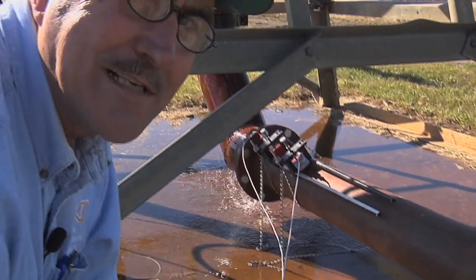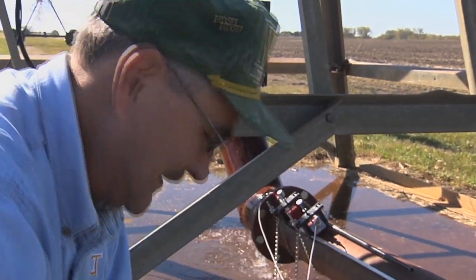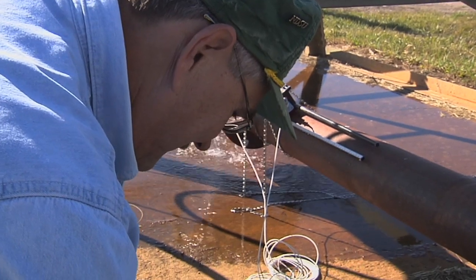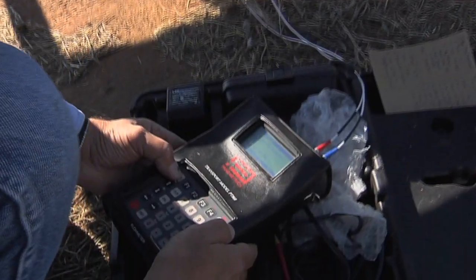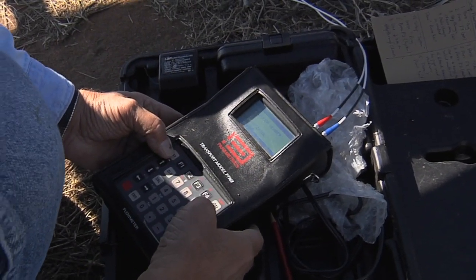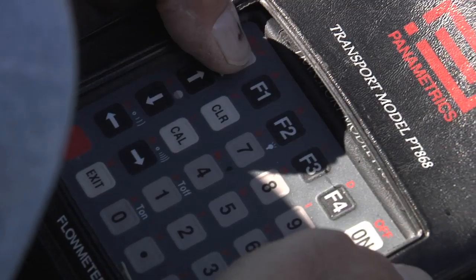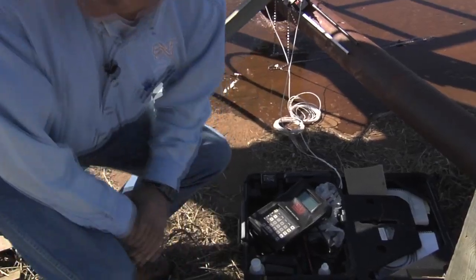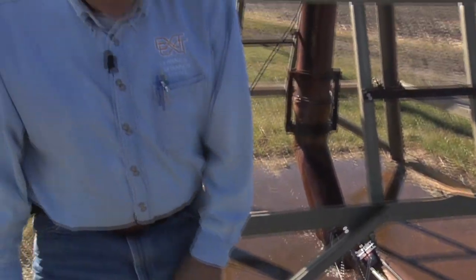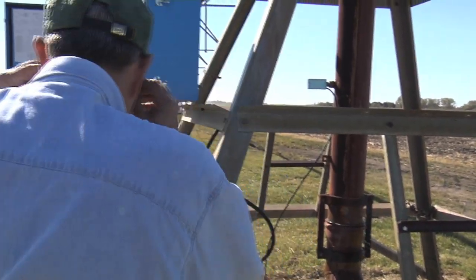You can put different types of transducers on these. So I'm just programming this to tell it what the setup here is. And there it'll calculate how far apart those transducers are. It's saying we got about 625 gallons a minute. And the end gun is not on.